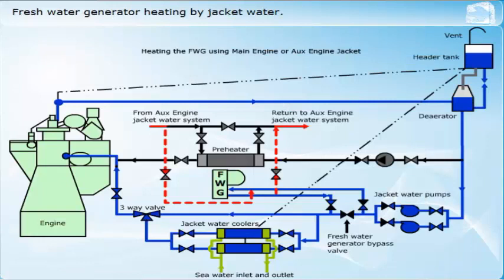The heat which is carried away by the jacket water originates partly from the combustion of fuel in the cylinder. When the heat is transferred from the jacket water to seawater, the heat is wasted — it is simply dumped into the sea. If any of the heat can be used for a productive purpose, the overall plant efficiency can be improved. One common means of achieving this is to use the heat from the jacket water to heat the feed and the generating element for a fresh water generator. This reduces the cost of fresh water production on board, as no additional fuel is required to provide the necessary heat energy, and also means that the fresh water generator is being used as a cooler for the engine jacket water cooling system.